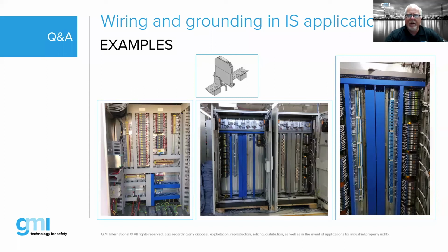The key thing is to make sure that if we are using Zener barriers on the inside of a panel, and we're mounting, say, our DIN rail to a steel plate, well, now all of a sudden we've basically taken that safety ground all the way to dirty earth, if you will. So if we're mounting Zener barriers on DIN rail, we want to use some sort of isolators to isolate that DIN rail from the dirty earth of the panel itself. There are different ways of doing it, and that's not the only way. Obviously certain panels might have a phenolic backpan as opposed to a metallic backpan. But basically, we need to make sure that we take that into account.